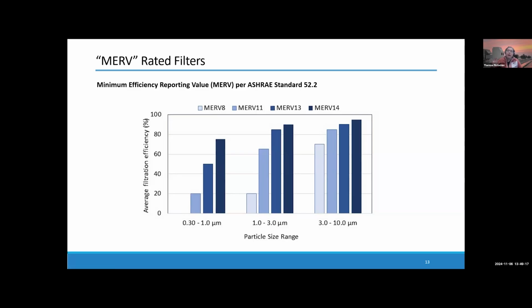And I'm going to show you at the end here a difference between what happens in a building if you have MERV 8 or you have MERV 13. But the absolute, if you do anything in your buildings, the best thing you can possibly do is get MERV 13 filters in there, because it's just a win-win-win. And most systems can essentially work with them.